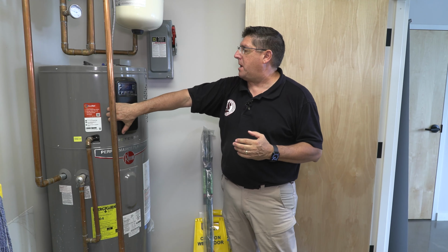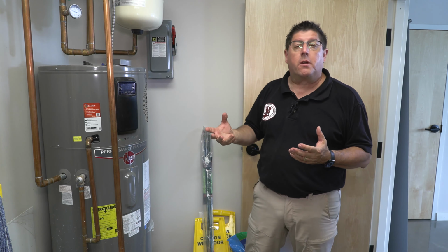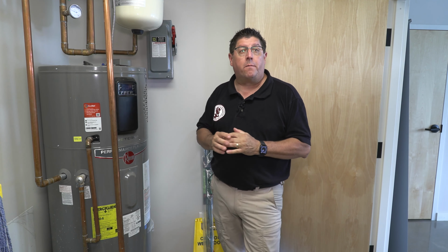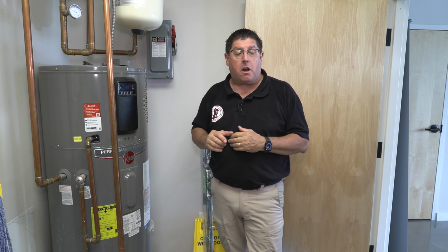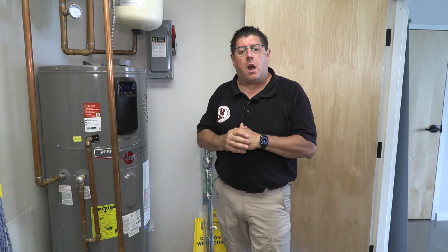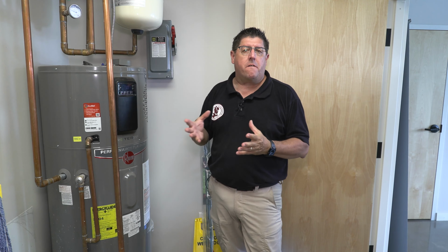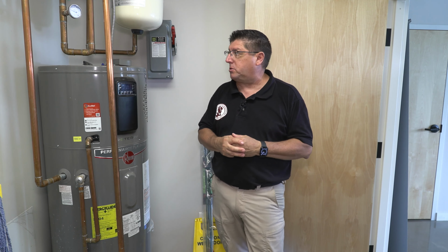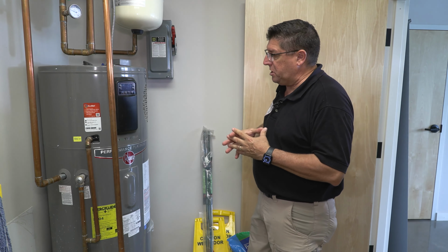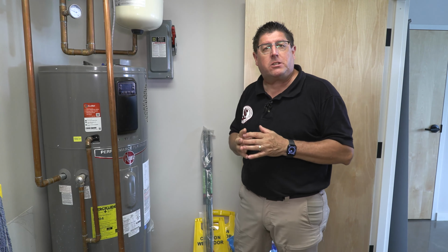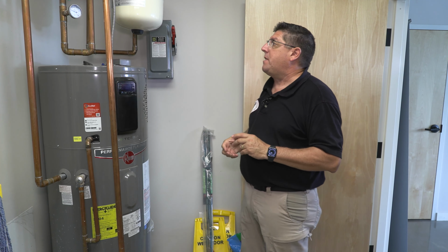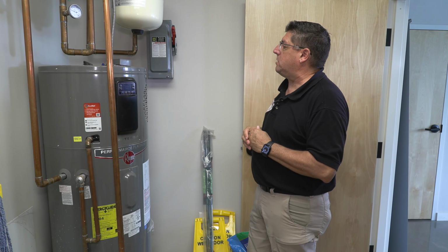It actually is set pretty high. This is a commercial building. We'll find a lot of times that the water from the hot water production is set a lot higher than residential. This one's actually set at 130 degrees, versus a residence, where you might set it at 105 or 110 degrees to prevent scalding. As we go through a commercial system like this, because we have a backflow preventer, we also need to have a thermal expansion tank on top of the water heater that helps regulate the system.